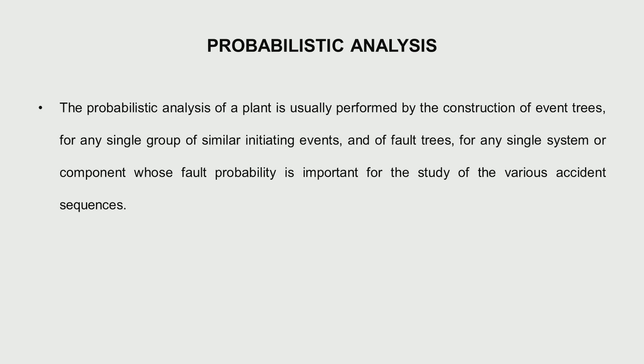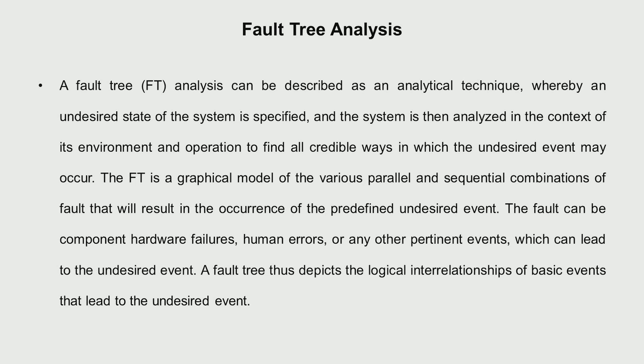How do we go about the probabilistic analysis? Here we talk about event trees and fault trees. For a similar type of faults or initiating events, we see what the consequence on the plant is or what the core damage frequency is — that is the event tree. For a single system to fail, what is the probability that single system can fail — that is the fault tree. A set of events lead to the event tree and finally the core damage frequency.